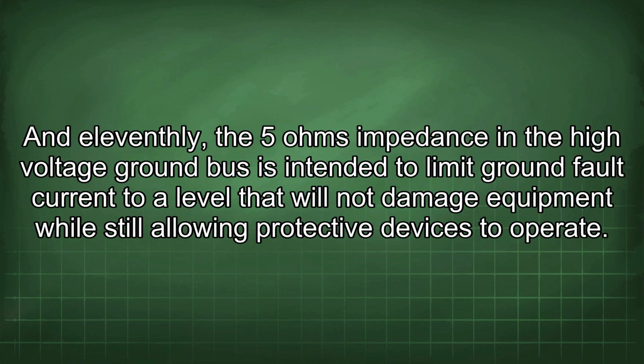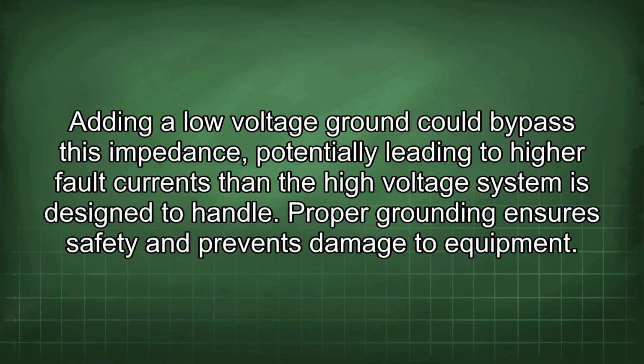And eleventhly, the 5 ohms impedance in the high voltage ground bus is intended to limit ground fault current to a level that will not damage equipment while still allowing protective devices to operate. Adding a low voltage ground could bypass this impedance, potentially leading to higher fault currents than the high voltage system is designed to handle. Proper grounding ensures safety and prevents damage to equipment.